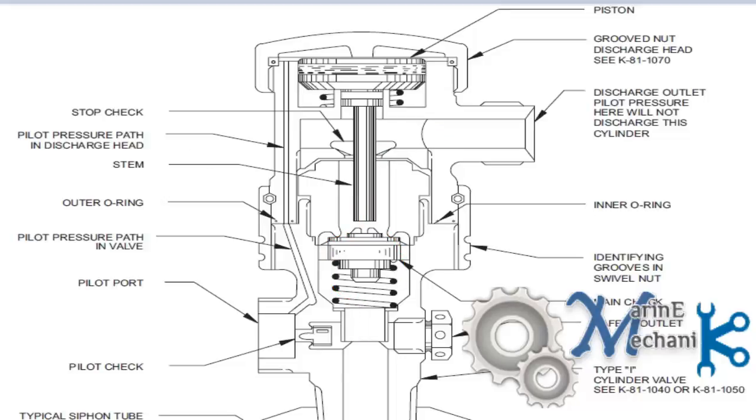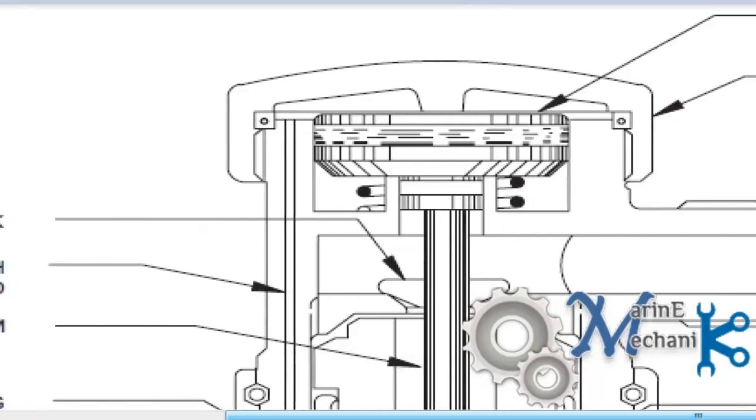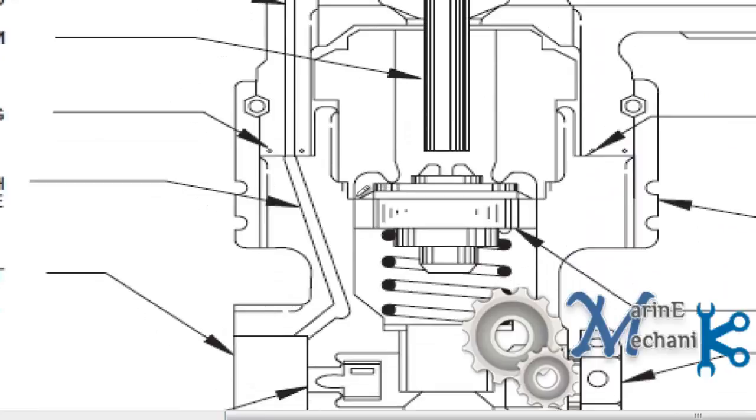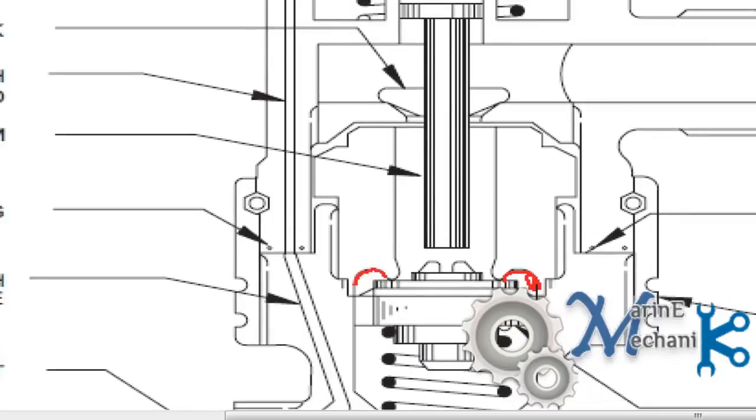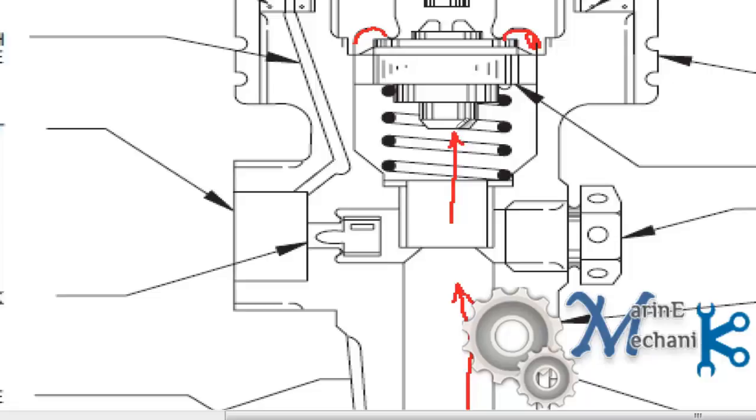One important thing what you have to note down here is there is a small curve, very fine curve given here. This is the CO2 as it comes here along with the spring force. Along with the spring force it keeps the valve shut. This is the main check valve. This main check valve is kept shut by the CO2 bottle pressure and the spring force. Thus the CO2 cannot escape out until the pilot CO2 comes and activates here.